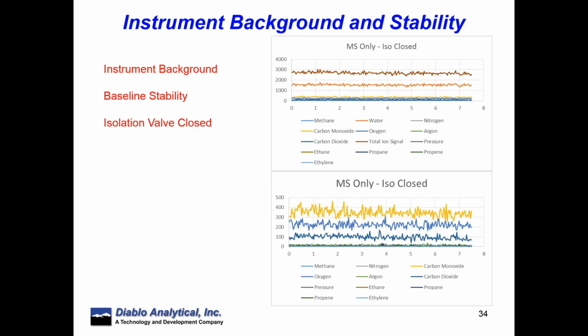Instrument stability is important. We've just shown you a baseline here. It's a very stable instrument. If you're doing acquisition over the course of days, sometimes there will be some drift and you'll have to compensate for that. There are various ways of doing it, but one is to periodically introduce your calibration gas from your cylinder, and then do an adjustment periodically due to drift.